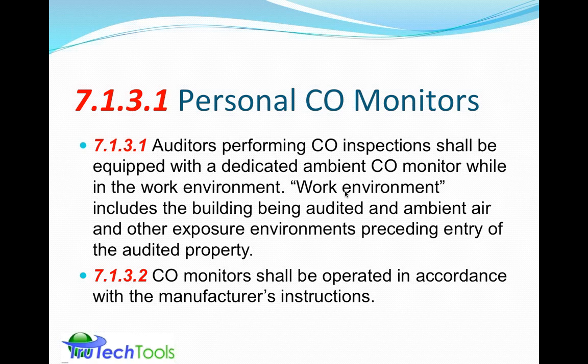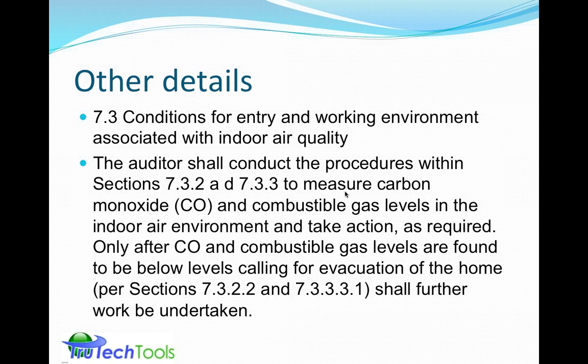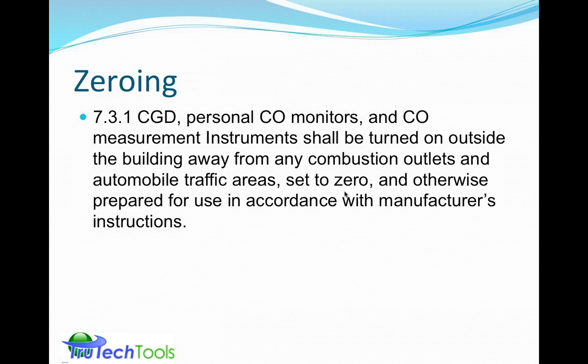To go a little bit further, of course, they say that it should be operated in accordance with the manufacturer's instructions, and then some details. You should conduct the procedures to measure carbon monoxide levels and take action as required. And only after the CO and combustible gas levels are found to be below the evacuation levels shall further work be undertaken. Now we'll go into what those levels are in just a moment.